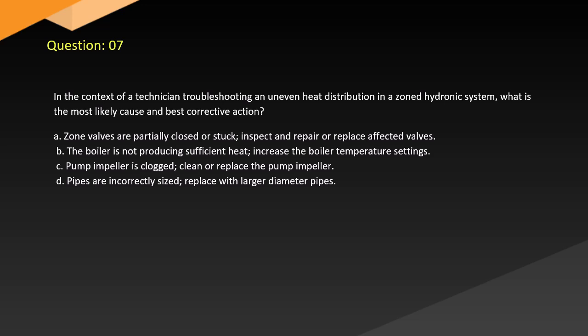Question 7. In the context of a technician troubleshooting an uneven heat distribution in a zoned hydronic system, what is the most likely cause and best corrective action? A. Zone valves are partially closed or stuck. Inspect and repair or replace affected valves. B. The boiler is not producing sufficient heat. Increase the boiler temperature settings. C. Pump impeller is clogged. Clean or replace the pump impeller. D. The pipes are incorrectly sized. Replace with larger diameter pipes.